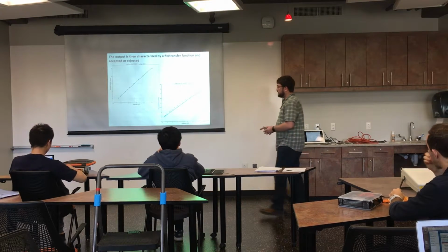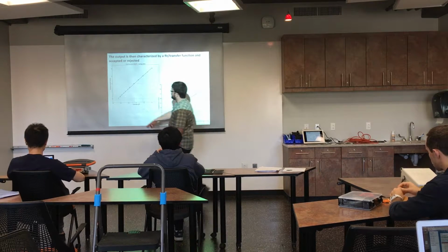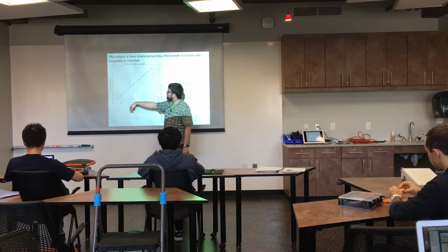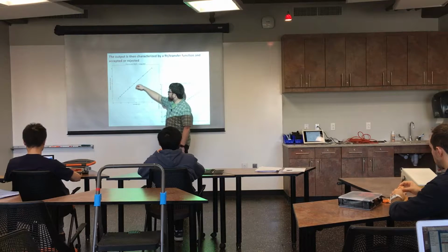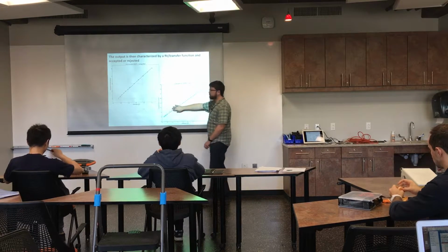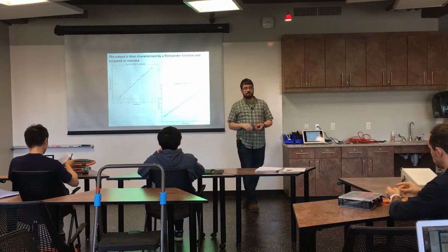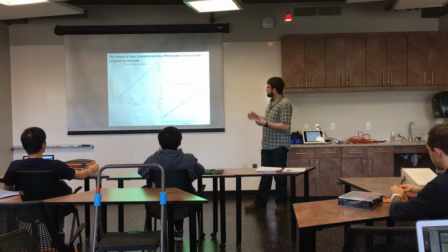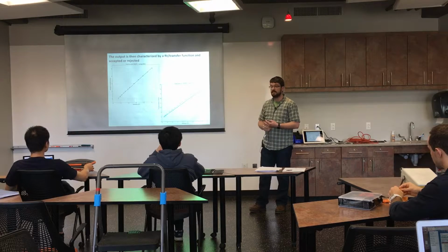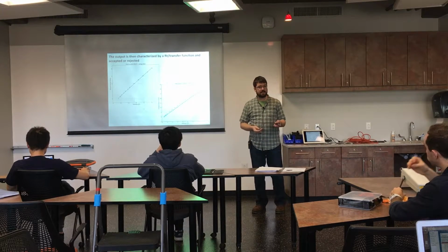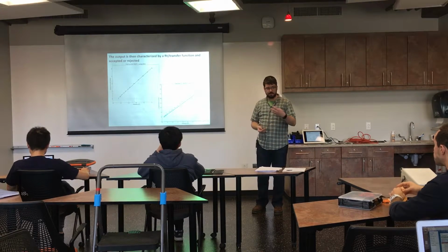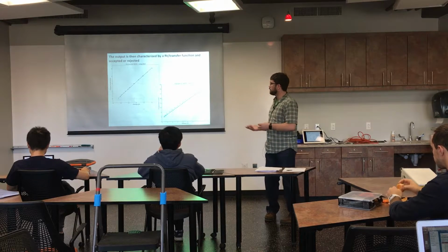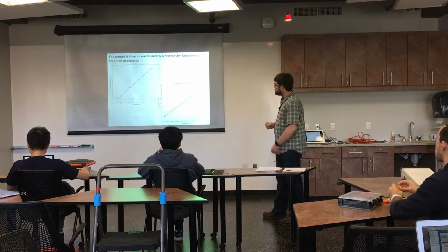And then you take your data set, where in this case we've gone through a number of displacements on a transducer from 0 to 8 millimeters, and we've got the output voltage. We've plotted it up, and luckily we're in the linear range of these sensors, so we get a very nice linear trend and we can fit a line to it. The slope of that line is the calibration factor that you're looking for, right? It's millimeters per volt, or volts per millimeter, however you want to frame that.